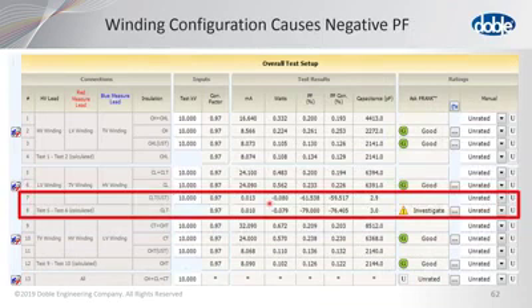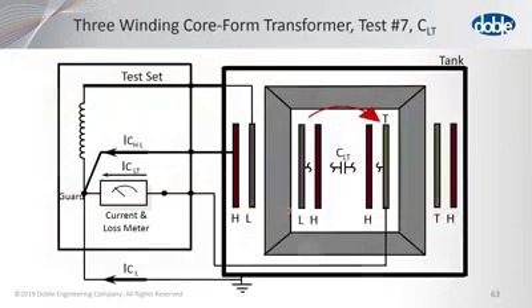The last case I wanted to show is where the winding configuration actually caused a negative power factor. Notice how low these currents are. This is like 1/100th of the limit, which we usually say is around 1 milliamp. So the engineer that was asked about this case went to the manufacturer and said, how is this transformer built? Why are we getting these results? And this is what they identified to him: the low voltage winding is on one leg of this single phase transformer, while the tertiary winding is on the other leg, and the high voltage winding is actually split between the two legs.